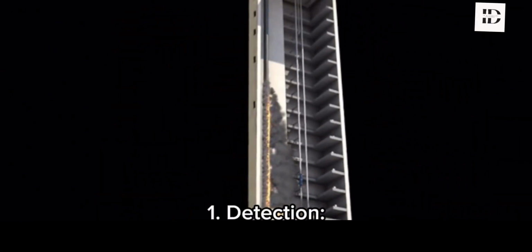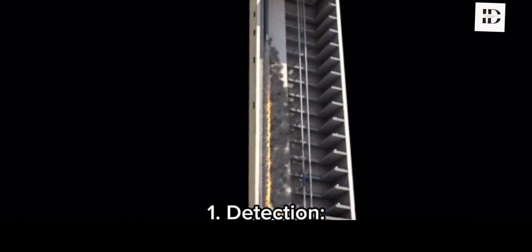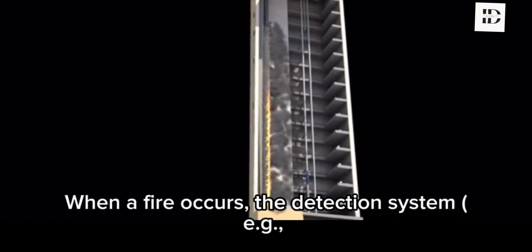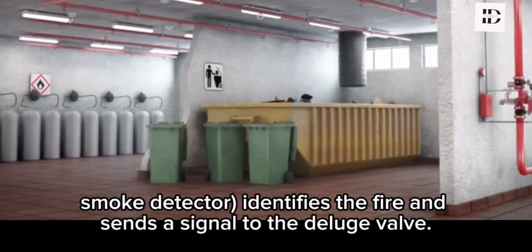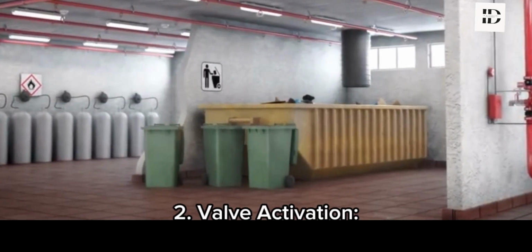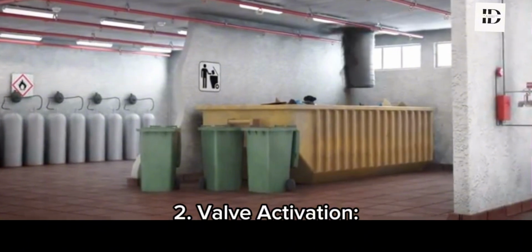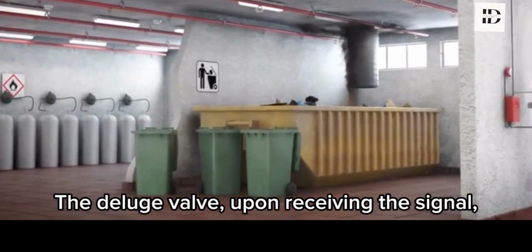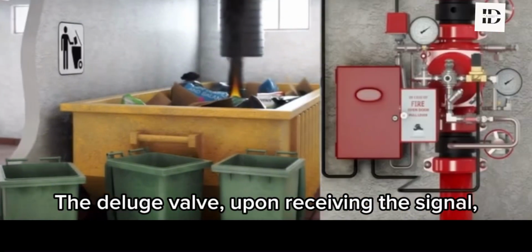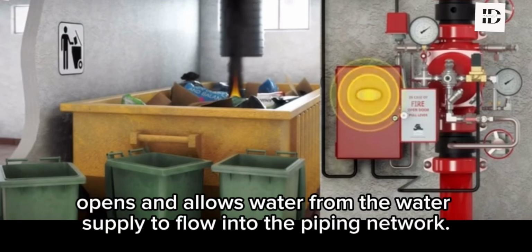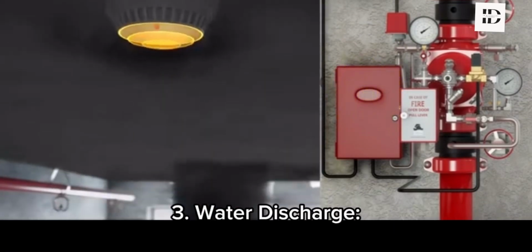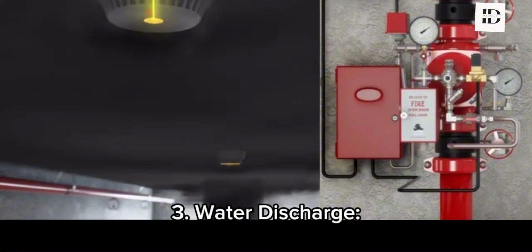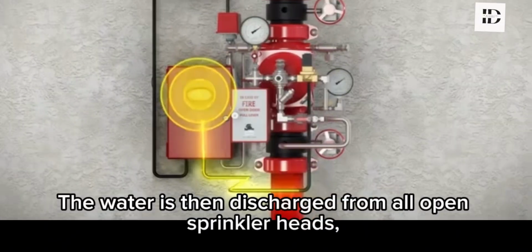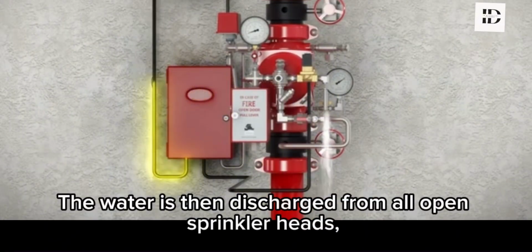1. Detection. When a fire occurs, the detection system, for example a smoke detector, identifies the fire and sends a signal to the deluge valve. 2. Valve activation. The deluge valve, upon receiving the signal, opens and allows water from the water supply to flow into the piping network. 3. Water discharge. The water is then discharged from all open sprinkler heads, creating a deluge of water over the protected area.